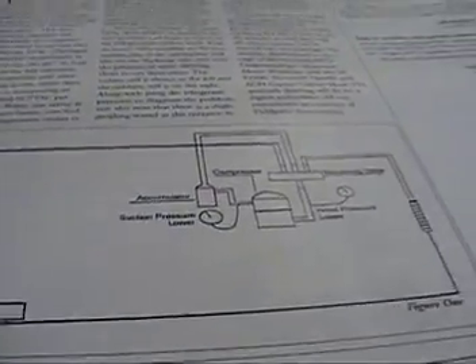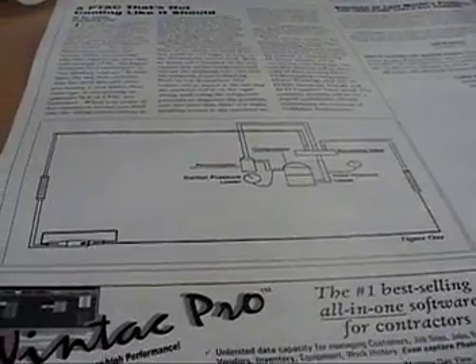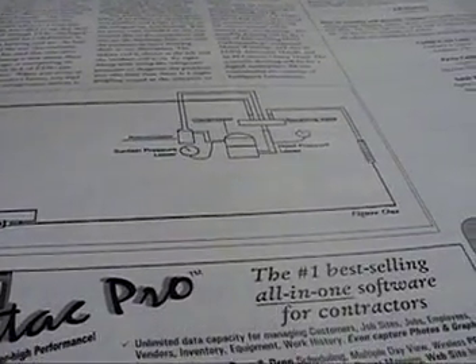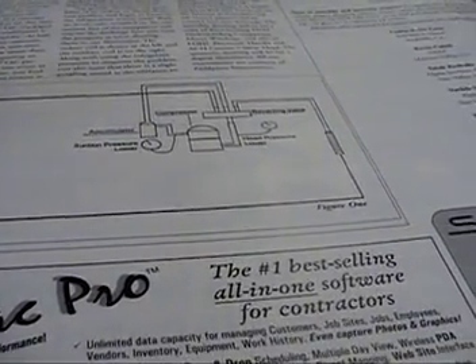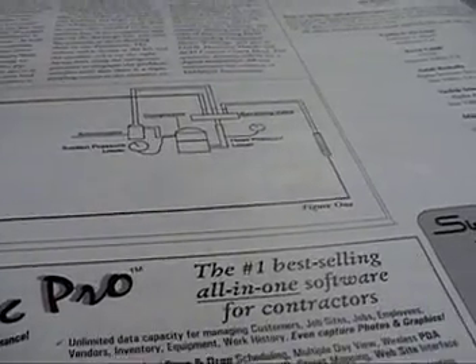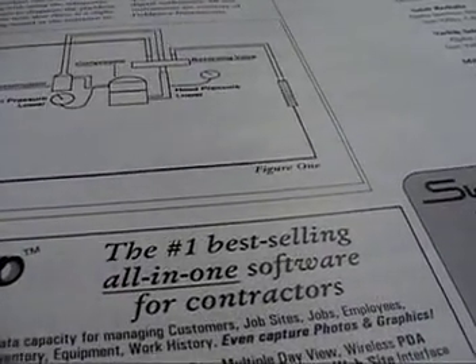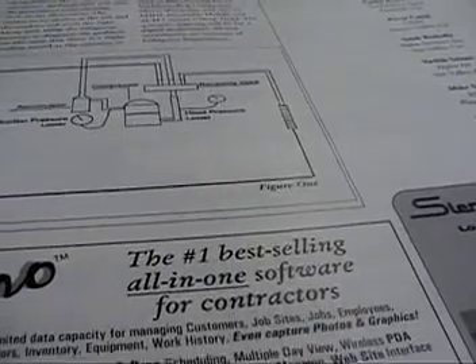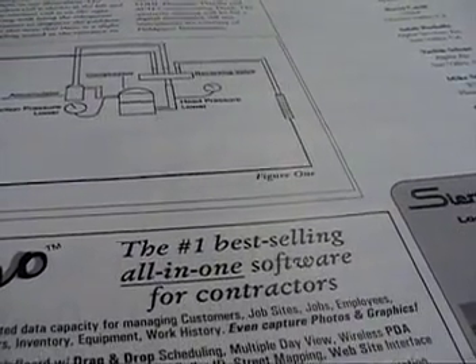The true suction line. Now, the true suction line is the middle one. Take a look at the little diagram down below. You see the middle one, the middle low pressure where it goes to the accumulator. That's where you would put your low pressure, that's where you put your line tap.